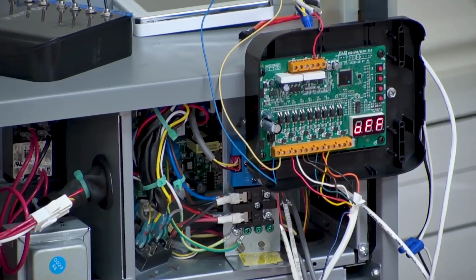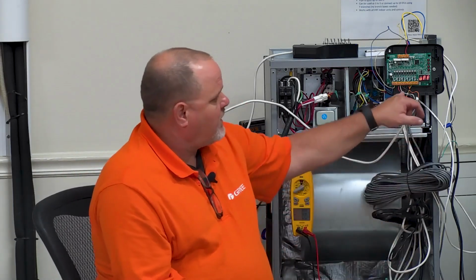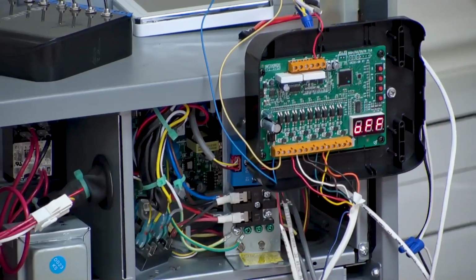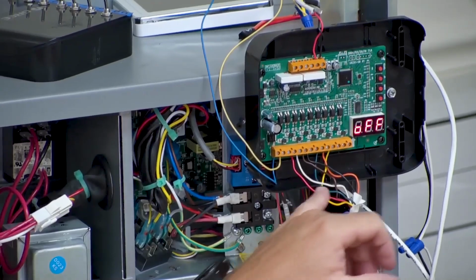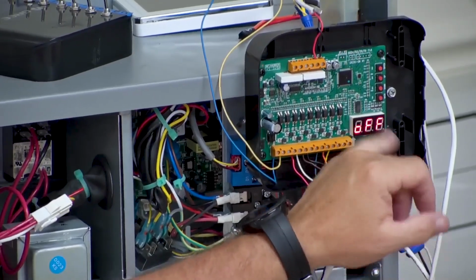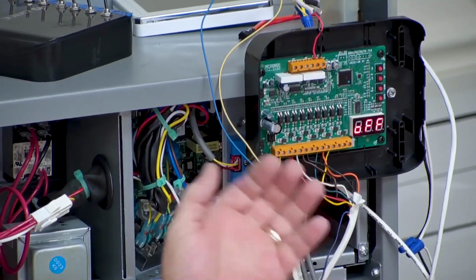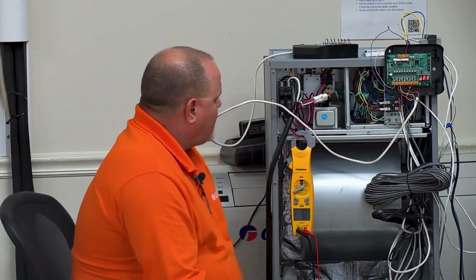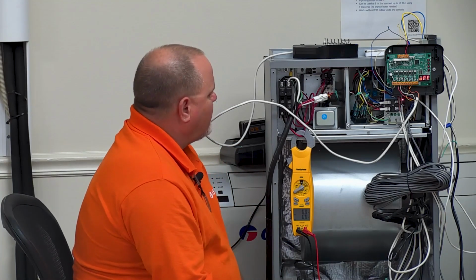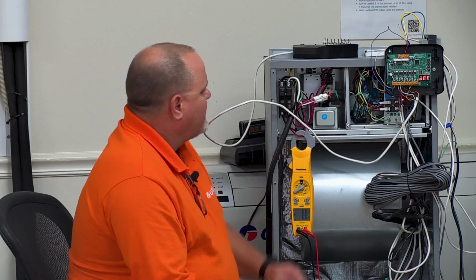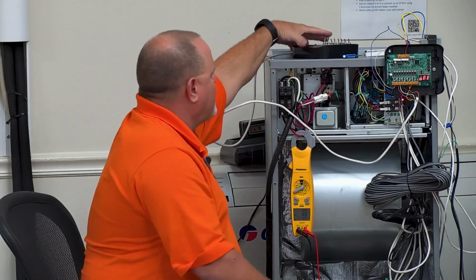So as far as the P codes go, I think that was all the major ones. Again, you guys are going to get a pamphlet in there. It'll tell you what the codes are. You just got to make sure you set it up, okay? Again, that P02, remember, that was only if you're wiring the G. Then you can select what fan speed you want to run on, whether it's auto, low, medium, high. But if you're using G1, G2, and G3, then if you got a call from G1, it would be running the unit at low speed. G2 would be medium speed. G3 would be high speed. I don't think there's anything else as far as setup goes. Nope, that's it. So just kind of give you a little bit of operational here.